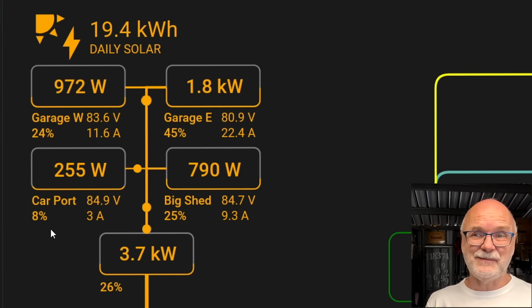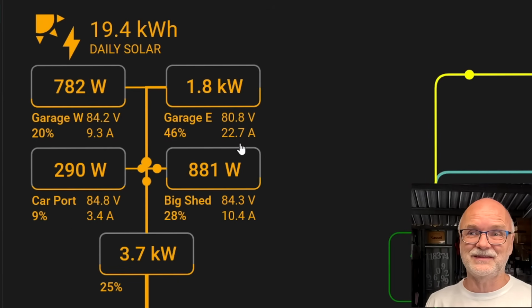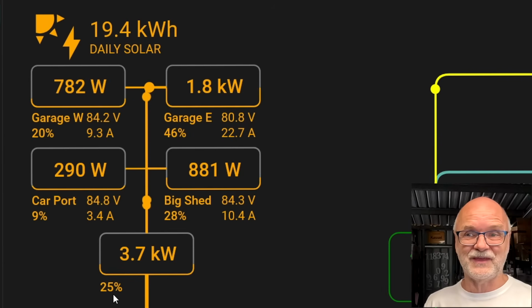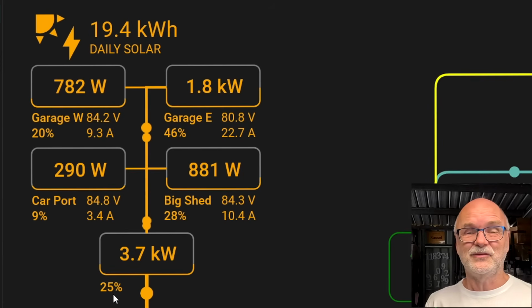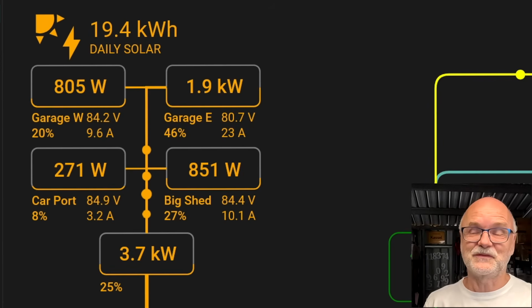You can see it here: carport 255 watts, 970, 1.8 kilowatt, 800 watts from here, 3.7. So that's 25% of what the system could deliver. The rest is limited because of this circuit breaker.